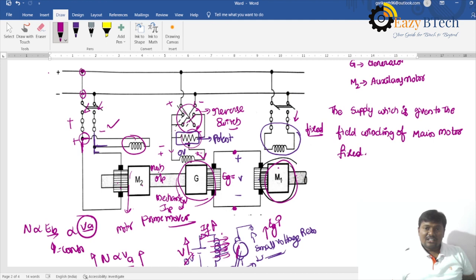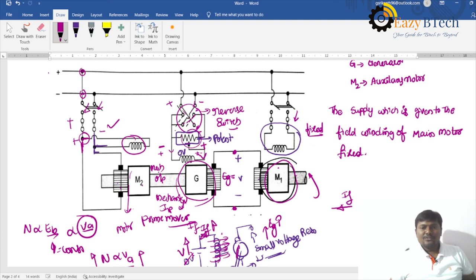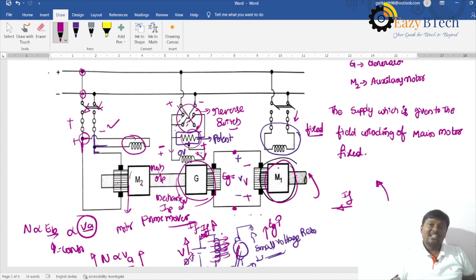To reverse the motor direction, the reversal switch is closed. This terminal becomes negative and this becomes positive, so the field current flows in the opposite direction, producing flux lines in the opposite direction. Consequently, the reverse voltage applied to the armature causes the armature to rotate in the reverse direction. That is the Ward Leonard speed control system.